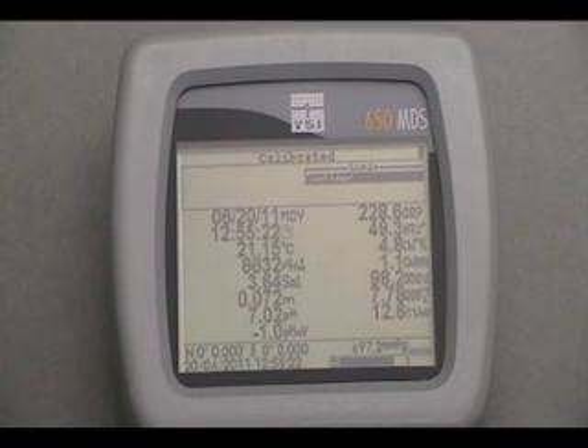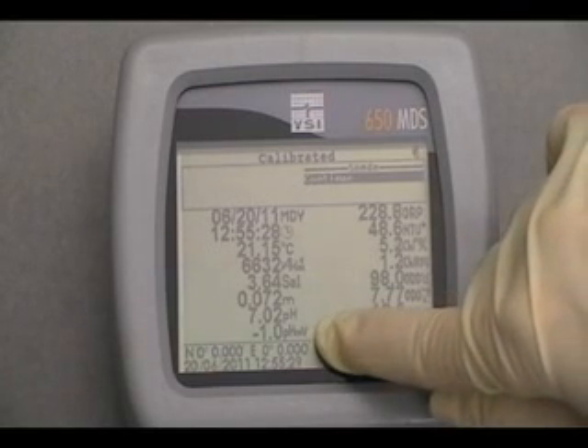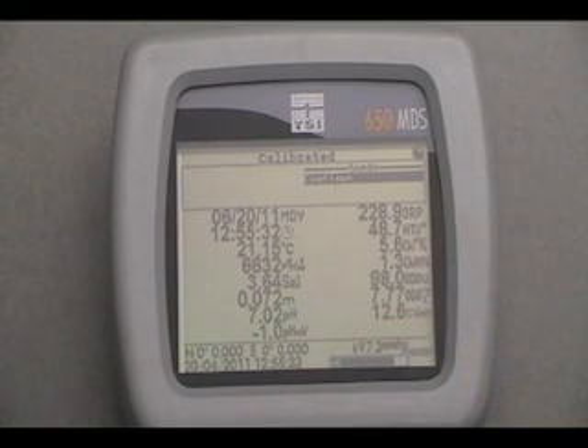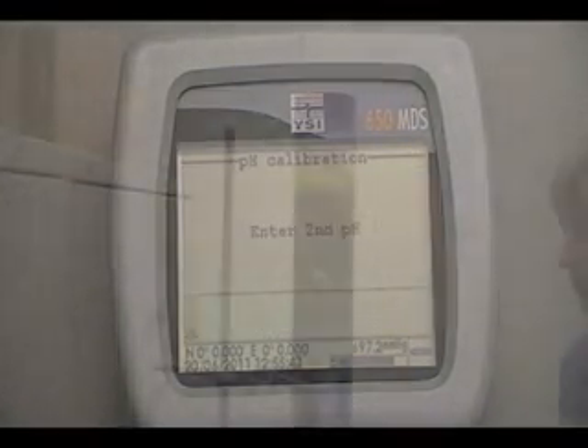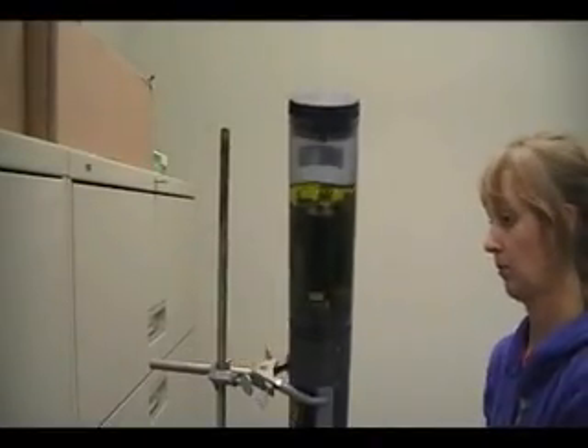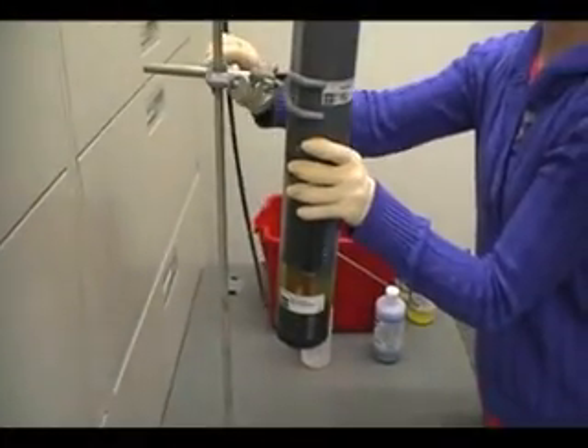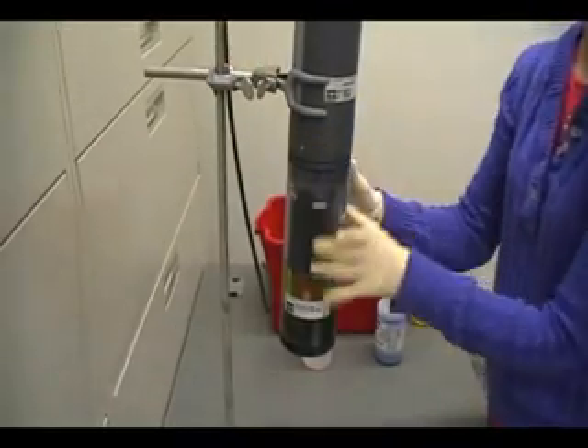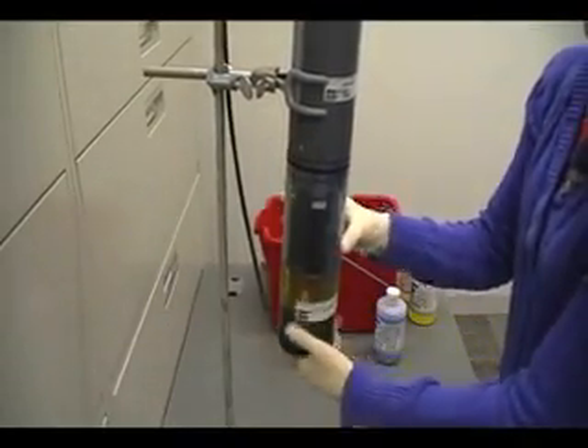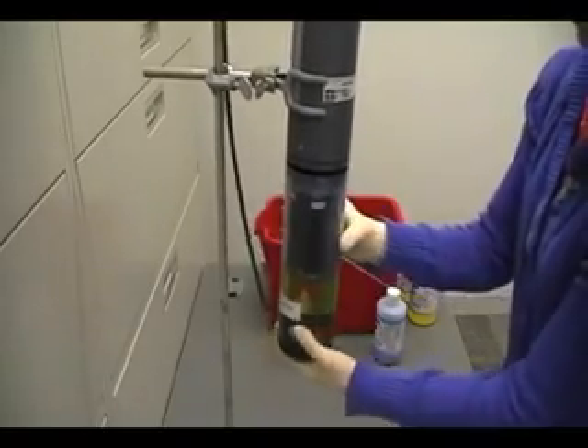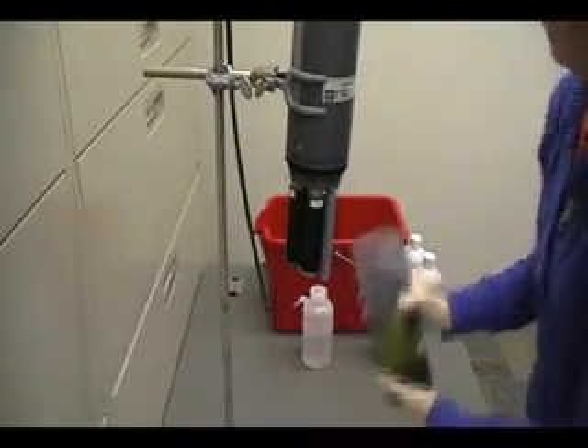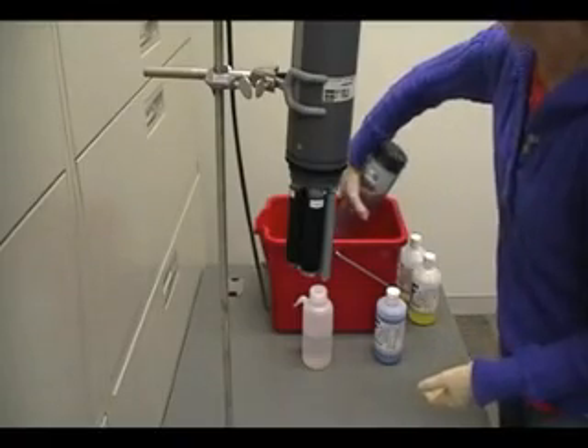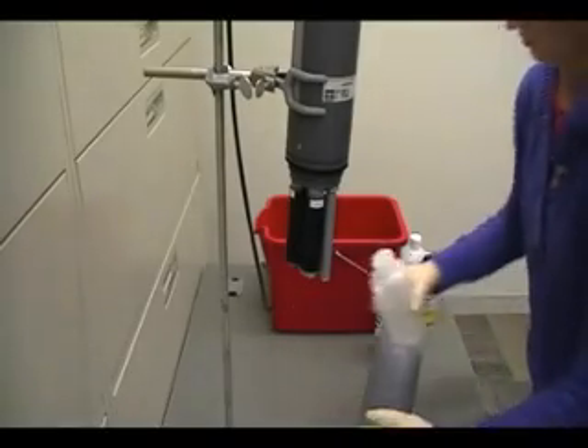Step 10. Record the post-calibration reading in pH units on your calibration sheet. Also record the post-calibration pH millivolts on the calibration sheet. The pH millivolts value should be between -50 millivolts and +50 millivolts. Press Enter to continue. Step 11. Return the sonde to the proper orientation. Empty the calibration cup. Rinse the sensors and calibration cup once with water.